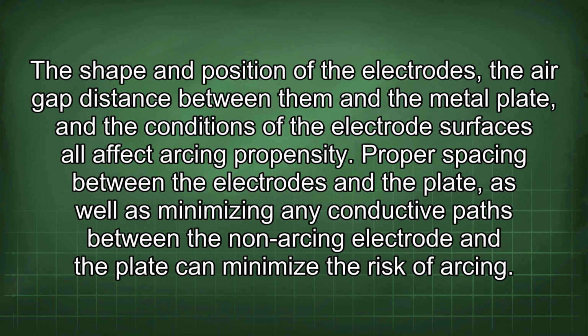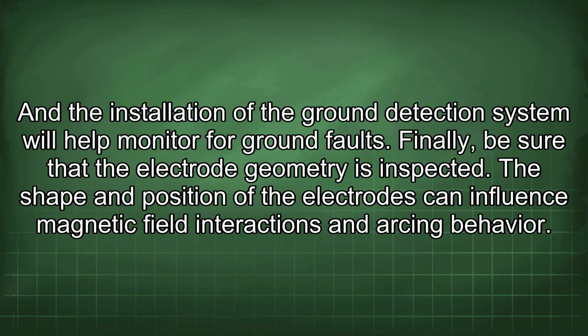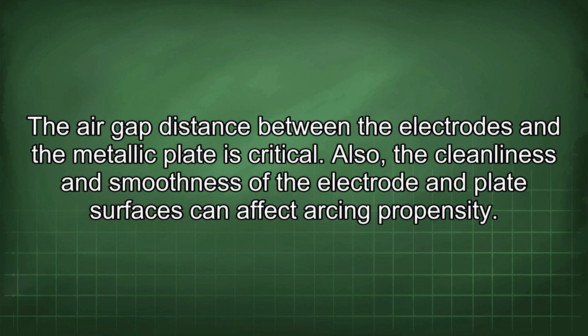The shape and position of the electrodes, the air gap distance between them and the metal plate, and the conditions of the electrode surfaces all affect arcing propensity. Proper spacing between the electrodes and the plate, as well as minimizing any conductive paths between the non-arcing electrode and the plate, can minimize the risk of arcing. And the installation of the ground detection system will help monitor for ground faults. Finally, be sure that the electrode geometry is inspected. The shape and position of the electrodes can influence magnetic field interactions and arcing behavior. The air gap distance between the electrodes and the metallic plate is critical. Also, the cleanliness and smoothness of the electrode and plate surfaces can affect arcing propensity.